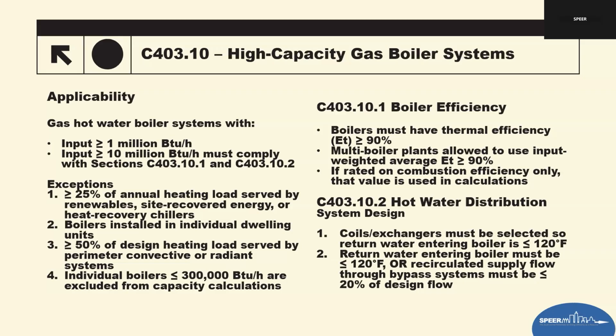This captures mid-size and large boiler plants but excludes small systems commonly found in small commercial buildings. The primary goal for this is to push boiler plants towards higher efficiency and better return water management, which significantly reduces energy consumption and improves condensing performance. So there are exceptions to this. The breakdown of that is there are 4. If at least 25% of the annual space heating is met with renewables, it's exempt. And then any individual boilers that fall under 300,000 BTUs per hour are ignored when calculating plant capacity.